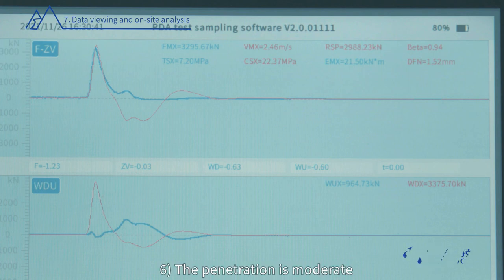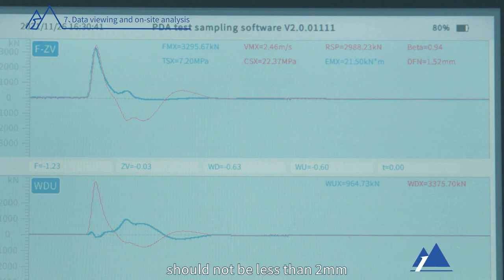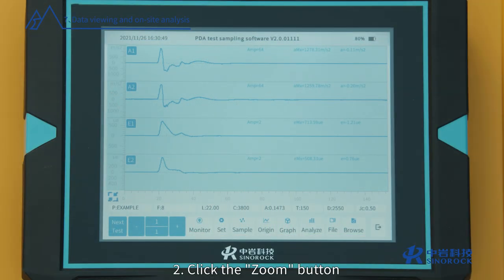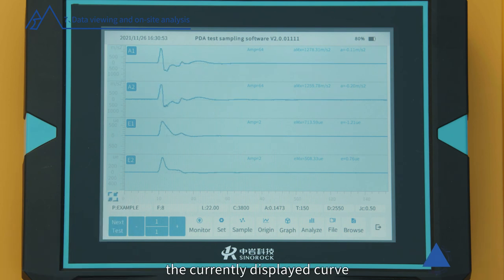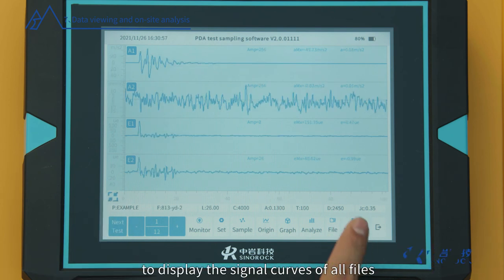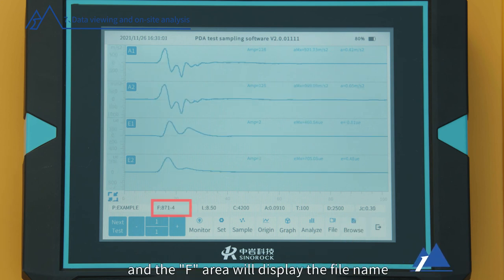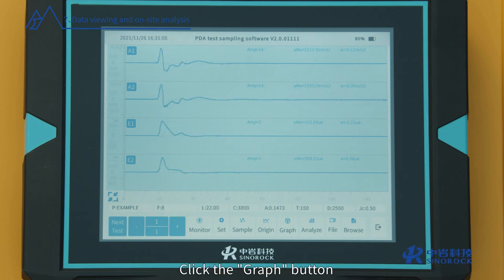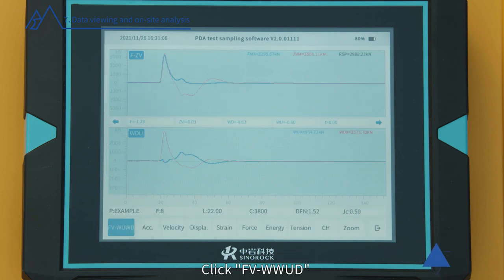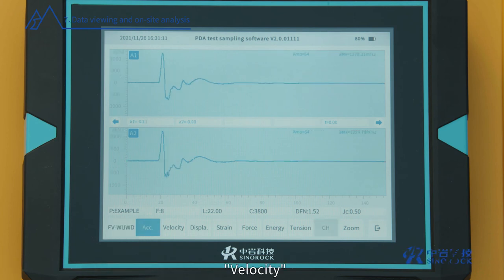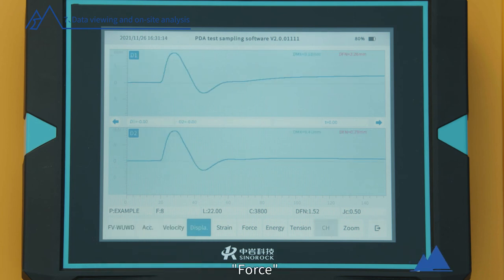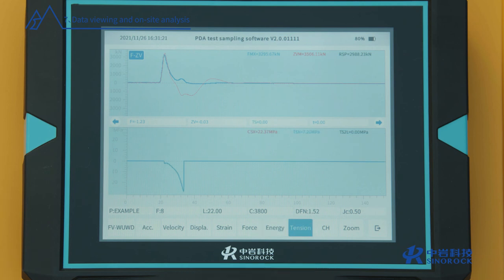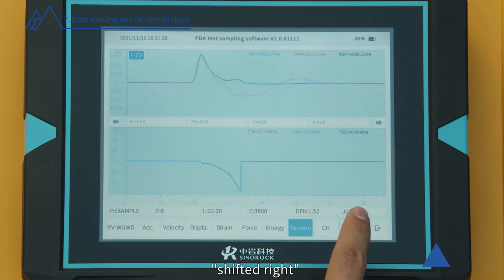Quality criterion (6): The penetration is moderate — generally, the single-click penetration should not be less than 2 millimeters nor greater than 6 millimeters. Step 2 — Click the Zoom button to zoom or expand the currently displayed curve. Click Browse to display signal curves of all files in the current save path in turn; the F area will display the file name of the opened file in real-time. Click the Graph button to enter the graph interface. Click FVWWUD, ACC, Velocity, Display, Strain, Force, Energy, or Tension for corresponding curve display in the curve display area. Each curve can be shifted left, shifted right, and zoomed.